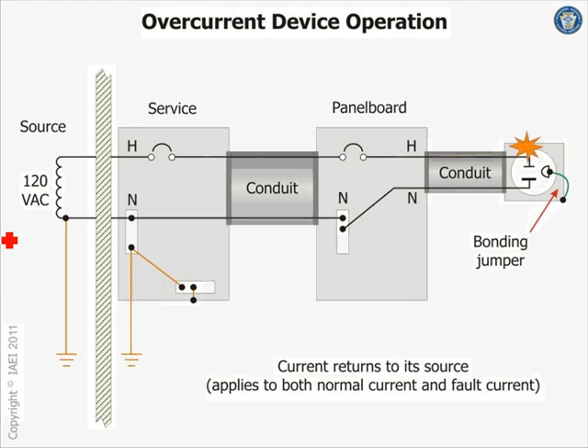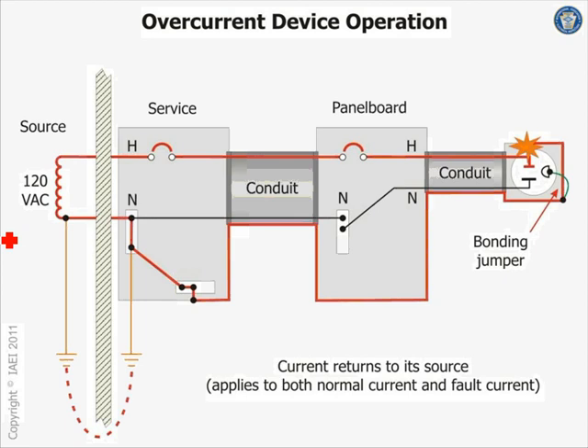Okay, now what happens if we have a ground fault in this situation, right? And remember, the box here is also bonded. When you have a ground fault, look what happened. Now we bypassed my plasma TV, my smart TV here, because my smart TV has a higher impedance. I have a parallel path between going through my plasma TV's high impedance and my very low impedance ground fault path. So most of the current will go right through the enclosure as your equipment grounding conductor all the way to the source. Your job and mine is to make this path Highway 494 or 35W, not the alleys of Minneapolis. Does it make sense?